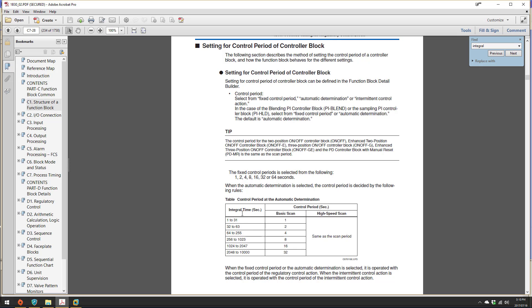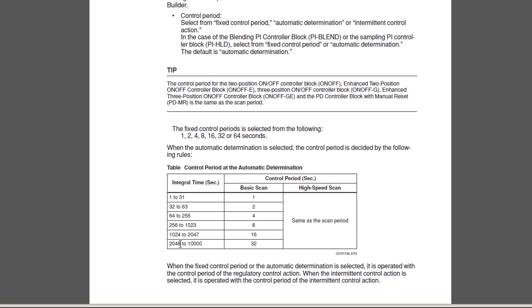The interval time of a PID block determines the actual scan time of the PID block. So if I change the reset time of a controller — say it's a fairly quick process with high proportional gain but a fairly long reset time — I might end up in a region where the PID block behaves in an intermittent fashion. In other words, it's only going to scan that PID block once every 32 seconds. This is probably a hangover to minimize CPU loading, and if you're not aware of it, it can cause some problems.